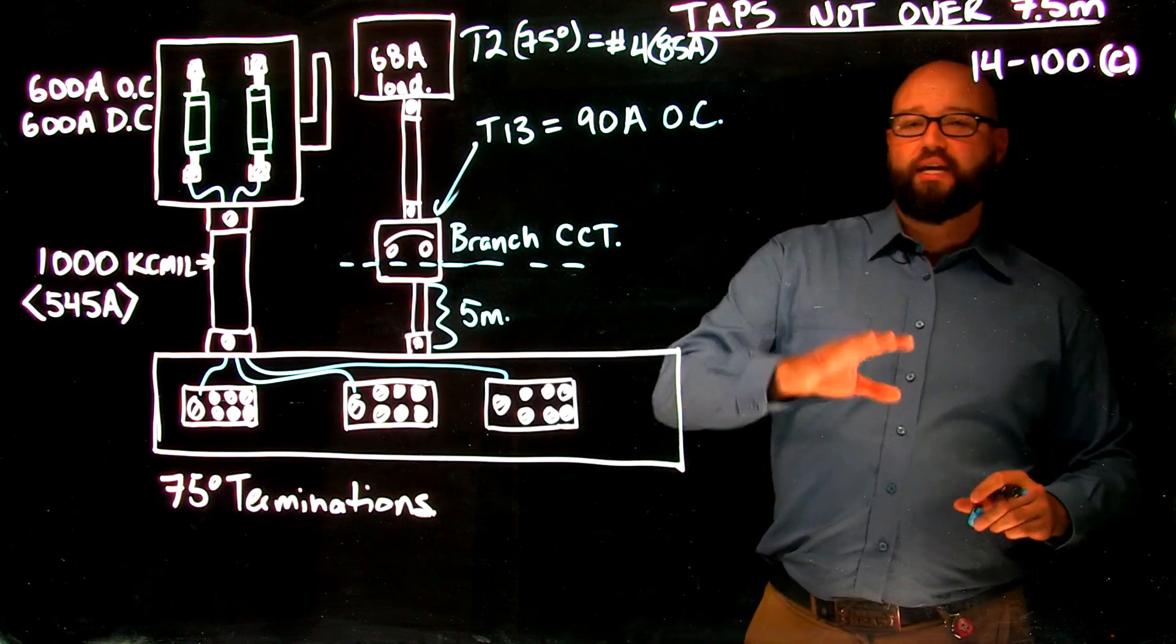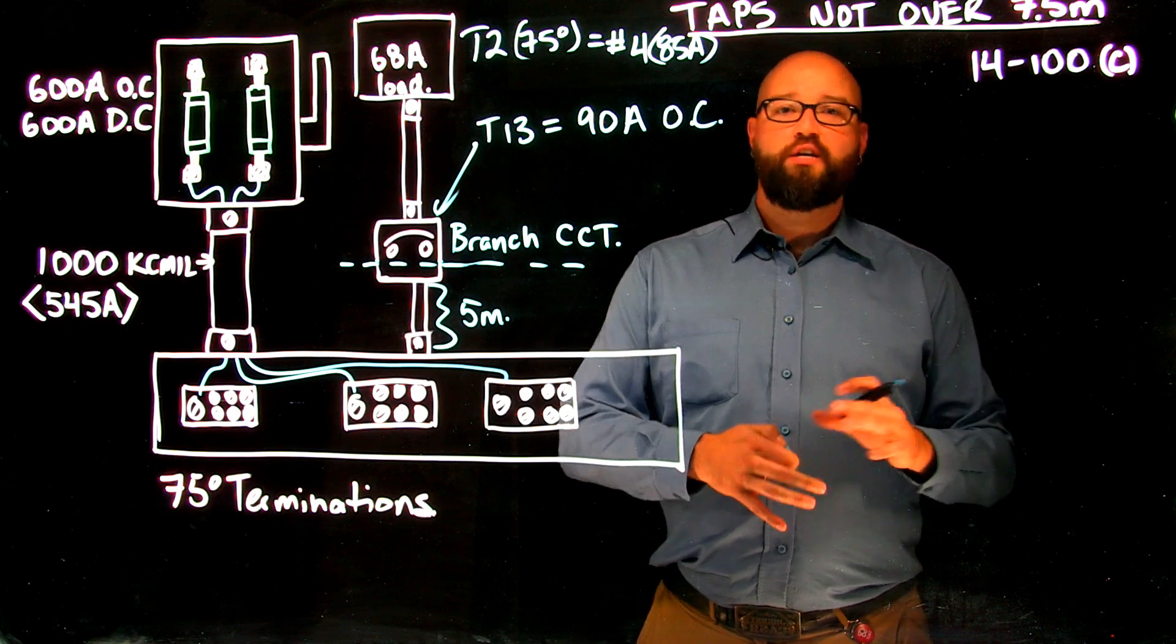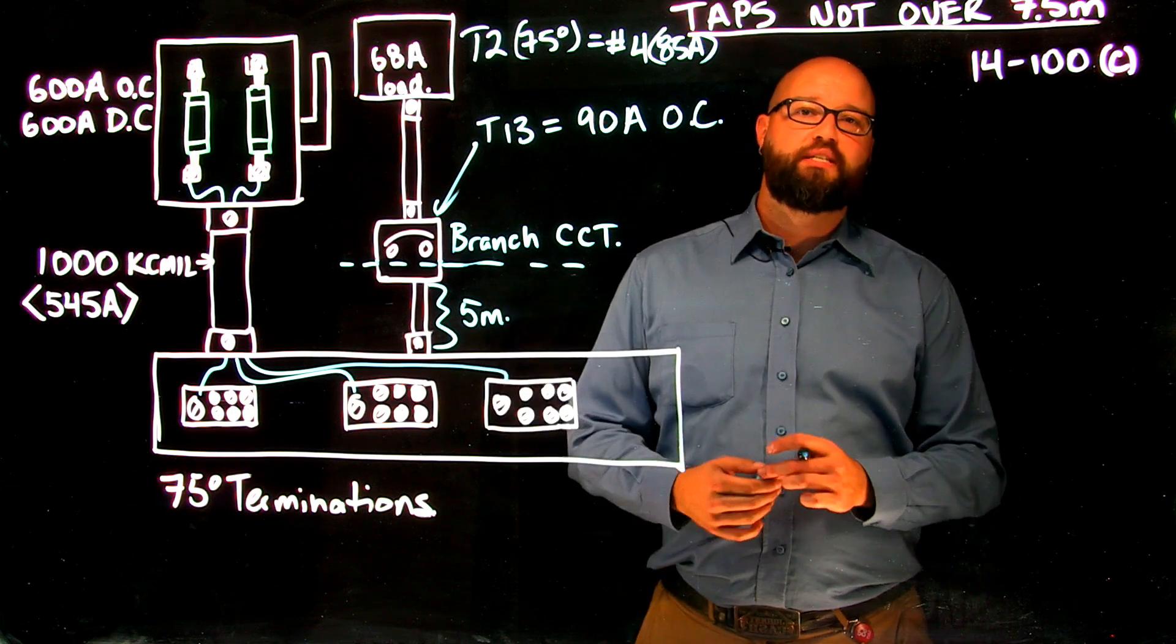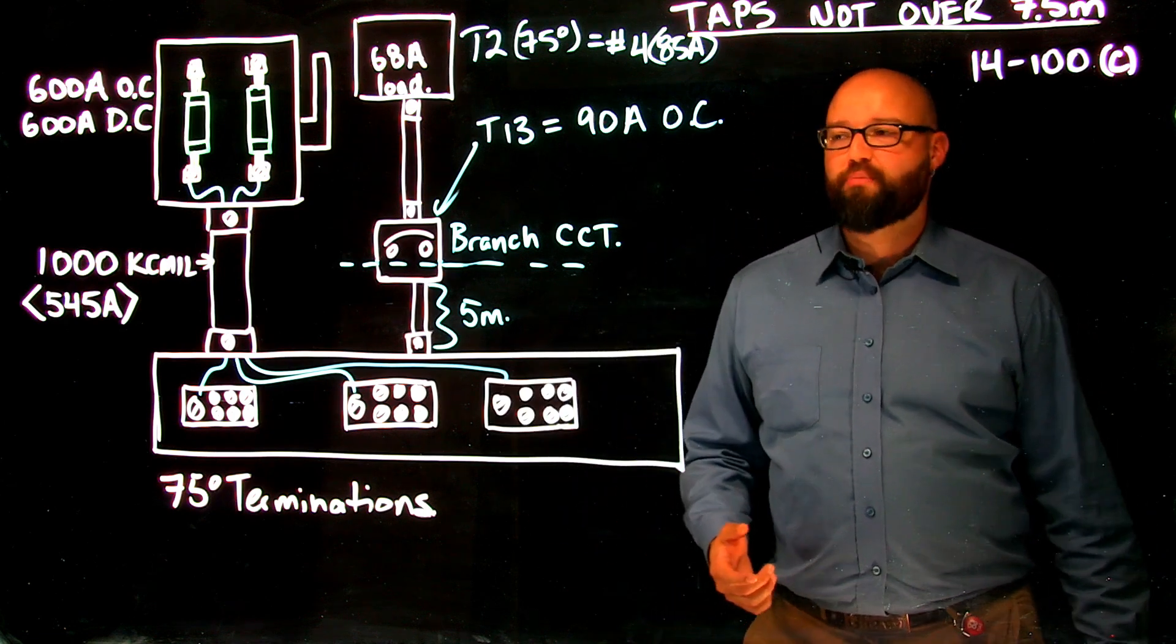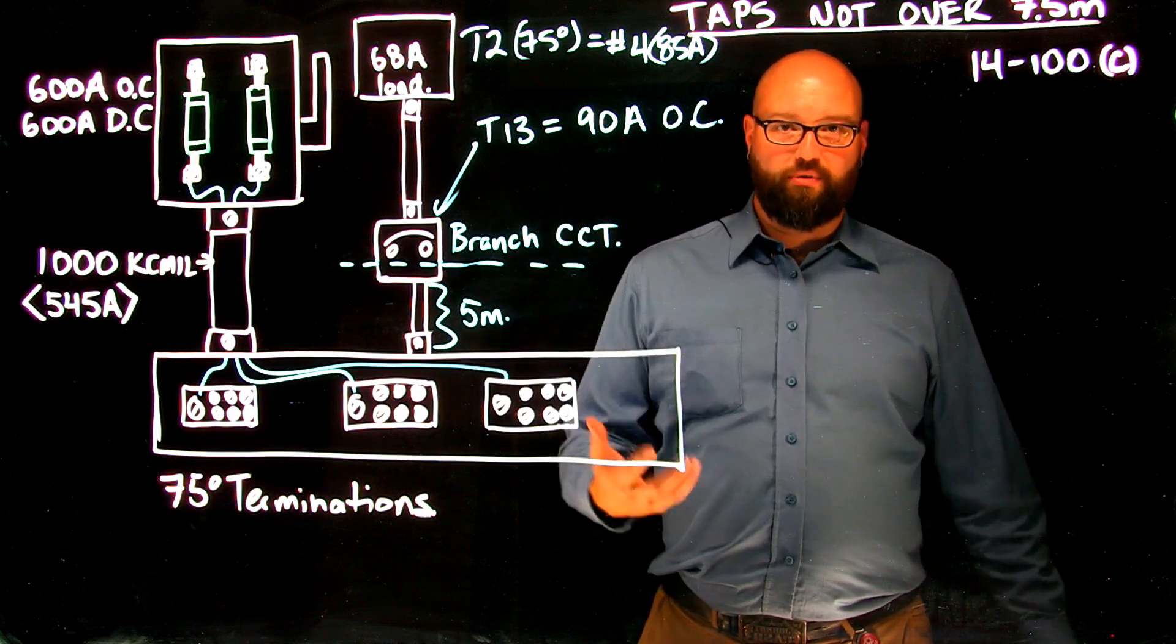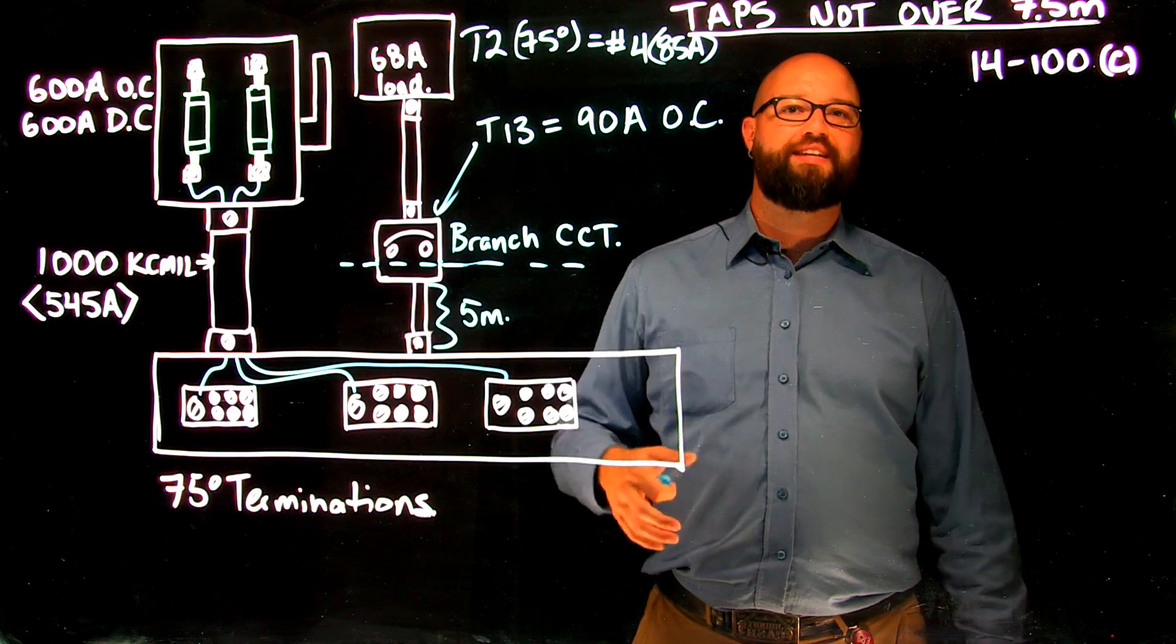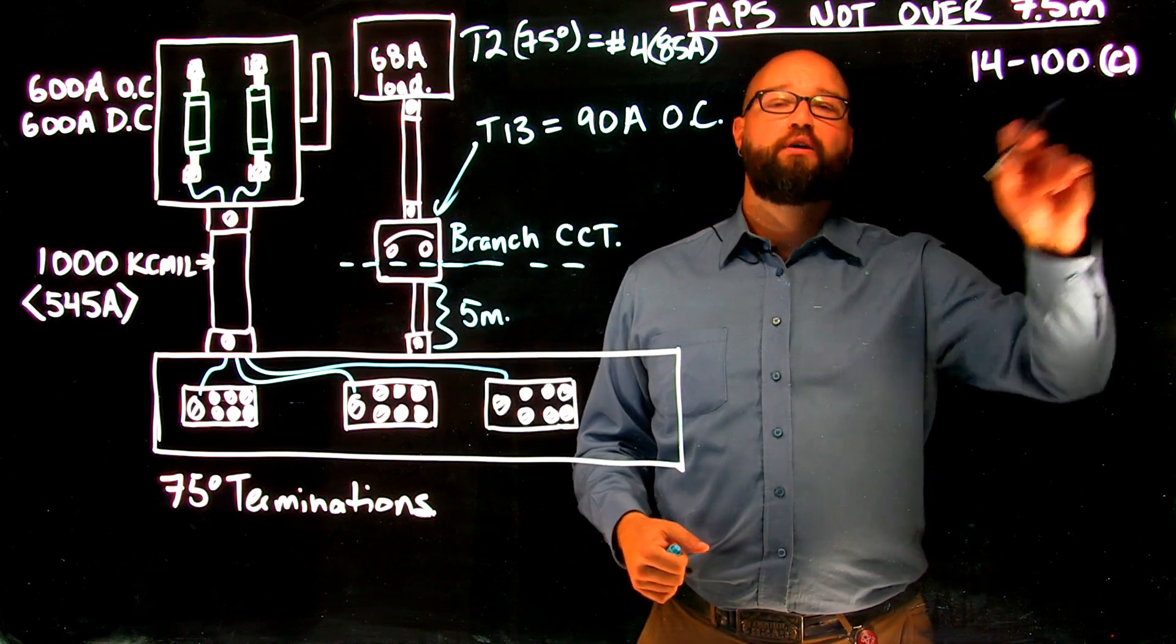So when we take a look at 14100C, what it tells us is this. Just like in 14100B, when I calculate the size of my tap conductor, I need to keep in mind my tap conductor has to have an ampacity greater than the overcurrent that it supplies. So in this case a 90 amp overcurrent, I would require a tap conductor that is at least 90 amps. So that's kind of the first choice that we have from item C.